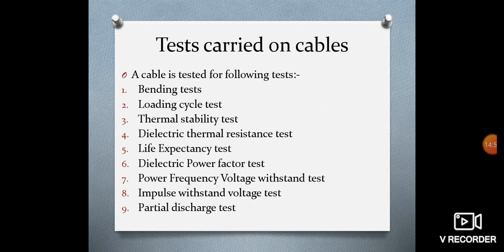In order to estimate the life of a cable, an accelerated life test is carried out by subjecting the cable to a voltage stress higher than the normal working stress. A high voltage Schering bridge is used to perform the dielectric power factor test on the cable sample.